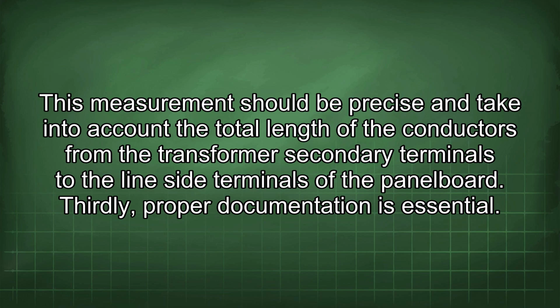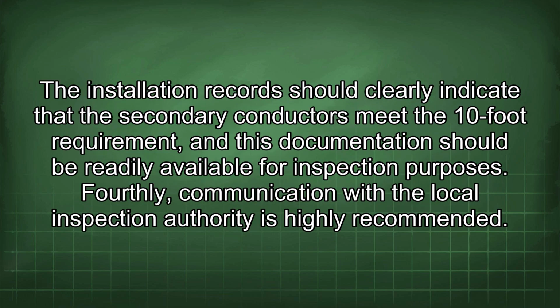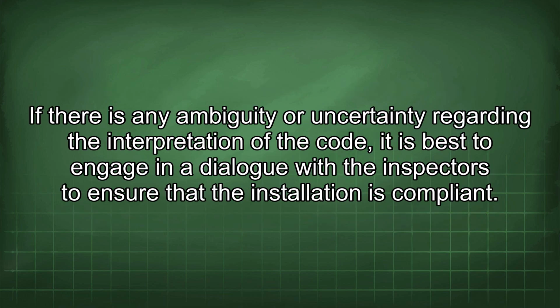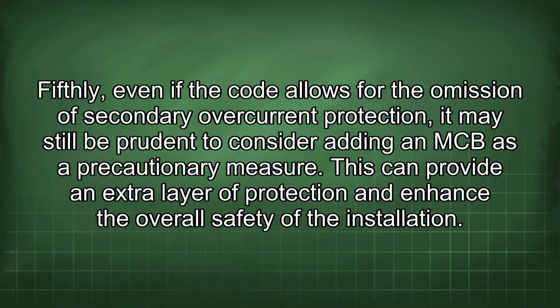Thirdly, proper documentation is essential. The installation record should clearly indicate that the secondary conductors meet the 10-foot requirement, and this documentation should be readily available for inspection purposes. Fourthly, communication with the local inspection authority is highly recommended. If there is any ambiguity or uncertainty regarding the interpretation of the code, it is best to engage in a dialogue with the inspectors to ensure that the installation is compliant. Fifthly, even if the code allows for the omission of secondary overcurrent protection, it may still be prudent to consider adding an MCB as a precautionary measure. This can provide an extra layer of protection and enhance the overall safety of the installation.